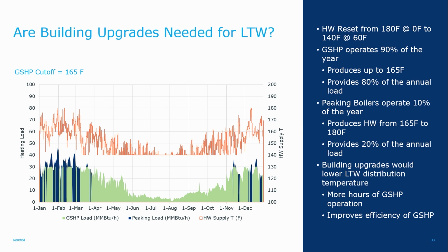In that case, the ground source heat pump operates 90% of the year and provides 80% of the thermal load. The peaking boilers only operate that remaining 10% of the year for 20% of the load. So it's another strategy, as opposed to just strictly looking at peaking and baseload.